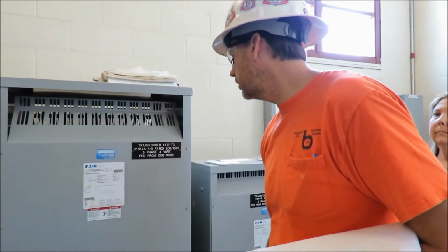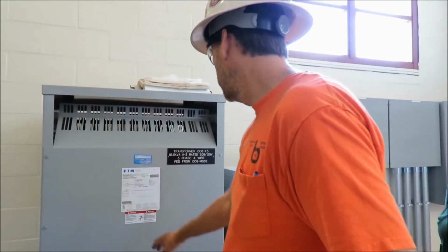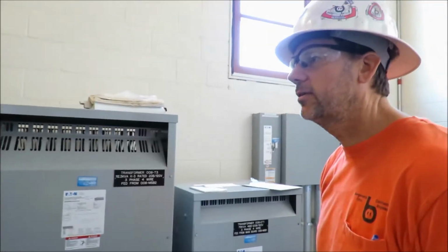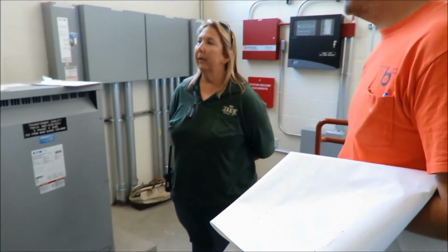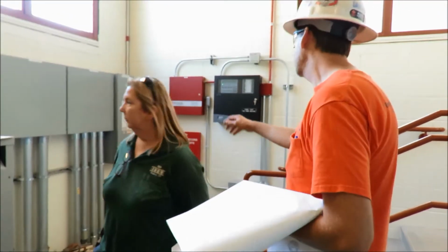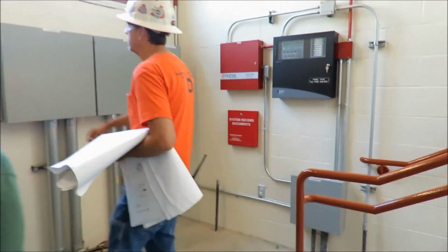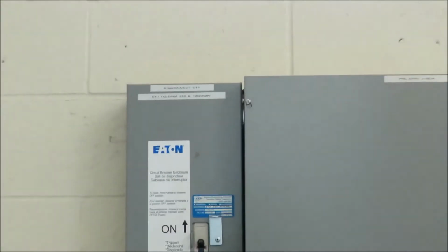And this one here is pretty much an isolation transformer. It comes in at the same voltage as it comes out. Those are for your isolated ground receptacles inside the building and for all the computer data, all the sensitive stuff. So it's pretty much an isolation transformer. And the disconnects for both these transformers are here, T1, T3, and this one here goes with a distribution board inside, PB2.